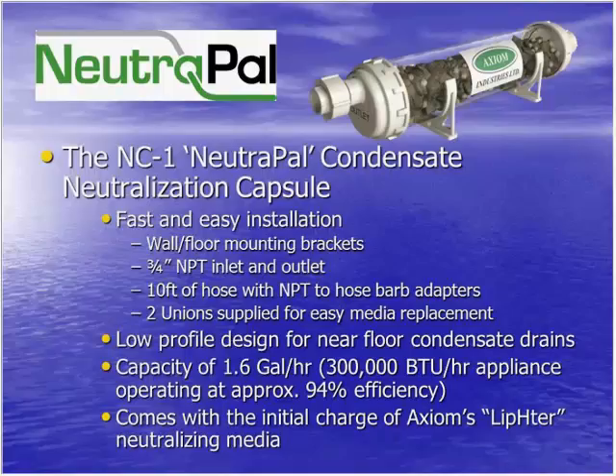But as you know, there are a lot of other things that can happen. If you do have poor quality combustion air, because it's essentially a trap, that's another thing I should point out is our capsules have an offset outlet to retain as much fluid inside the capsule as possible to ensure that the resident time or the contact time in the media is maximized, but things collect in there. So as I mentioned, poor quality combustion air, these things are going to collect in the trap and coat and block these things.